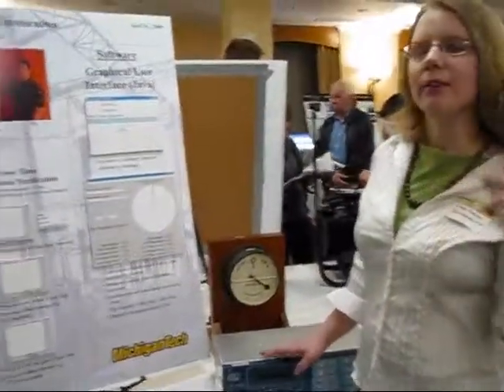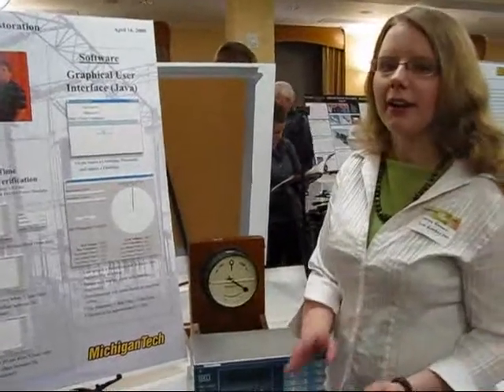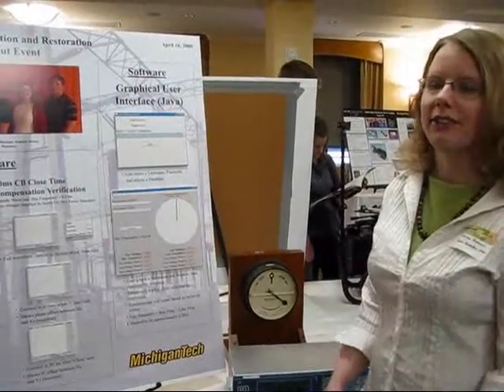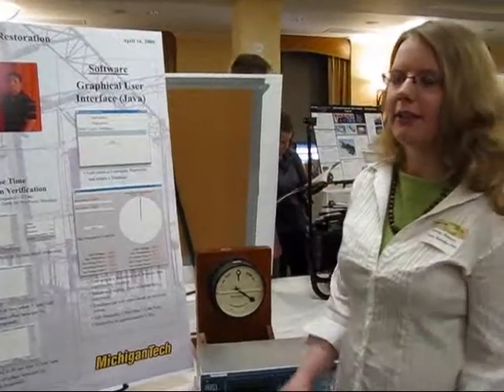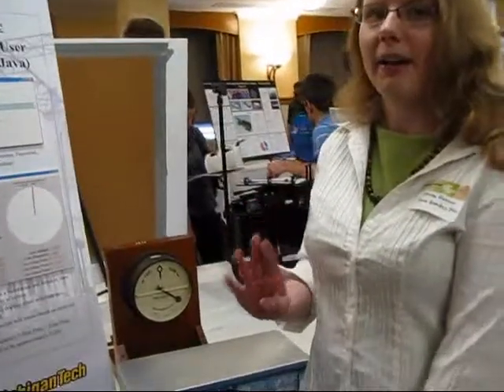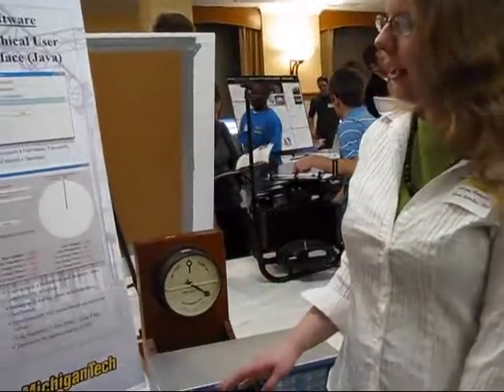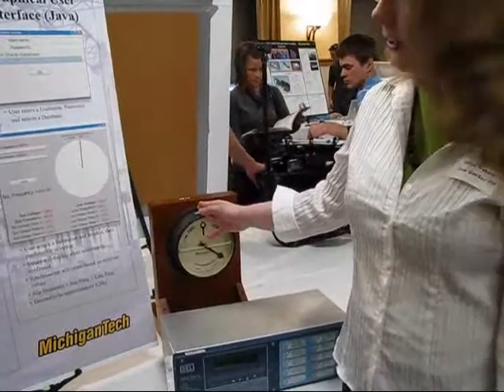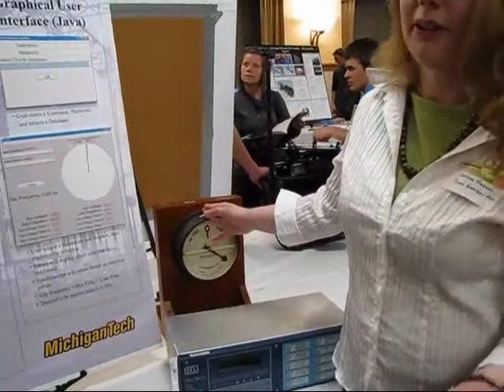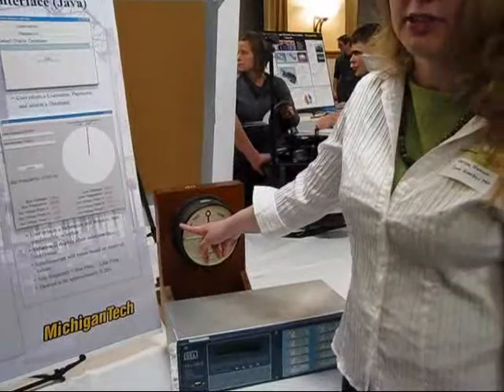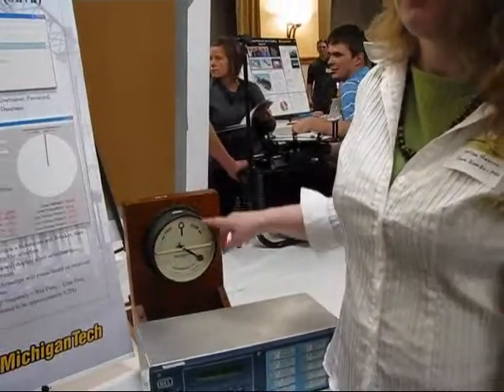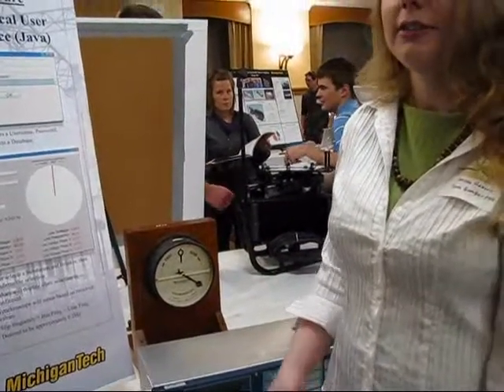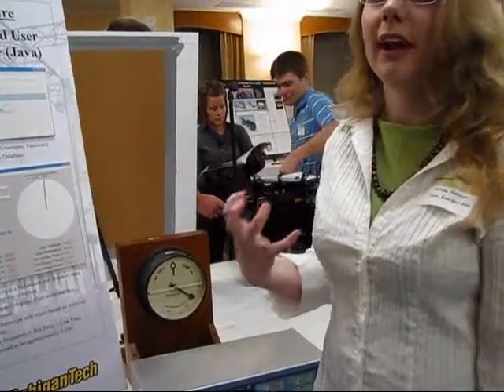Right now it's manual, so the technician has to drive out there, call back either generator, and tell them to turn it down or turn it off. There is also human error involved because you can't close it right at zero — there is a circuit breaker time delay. It's a big circuit breaker, so you have to close it at a certain time while the needle is rotating, which introduces human error.